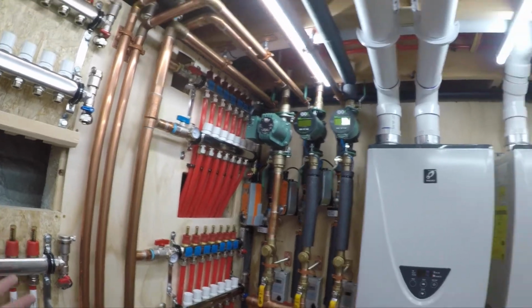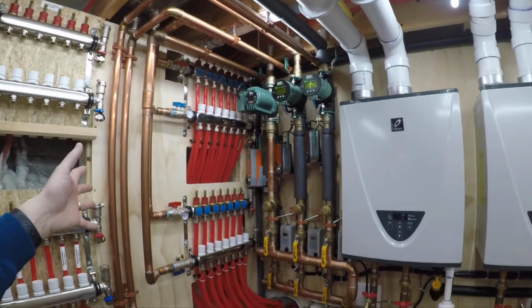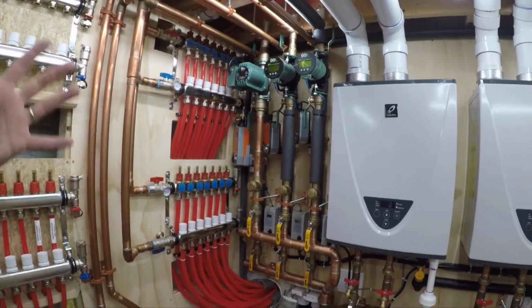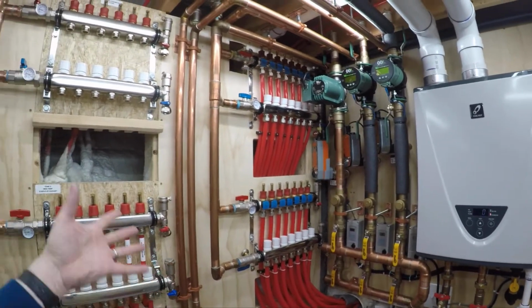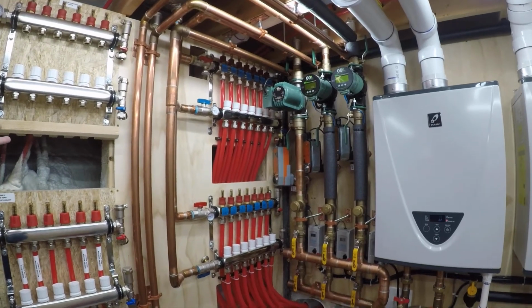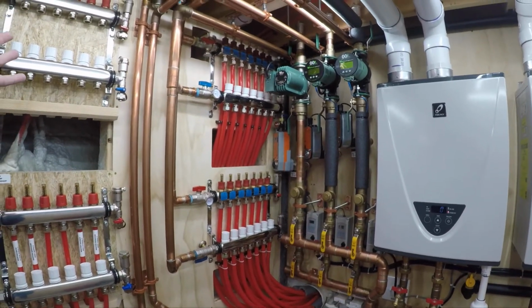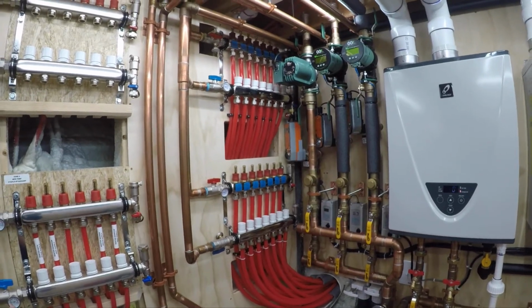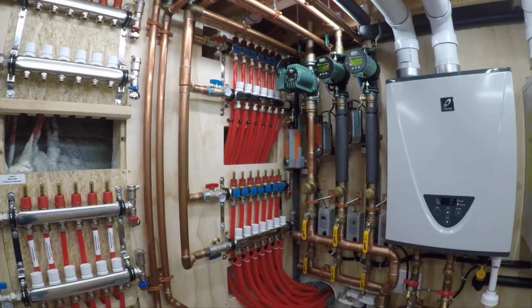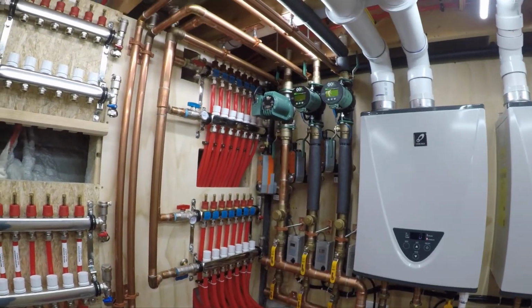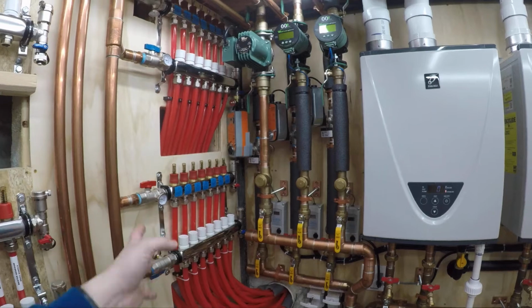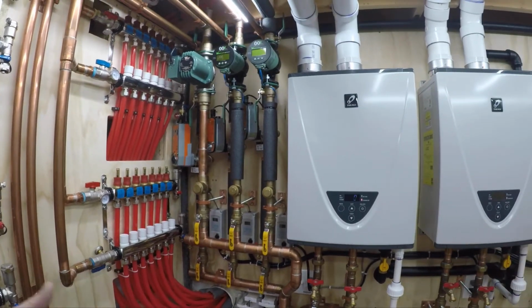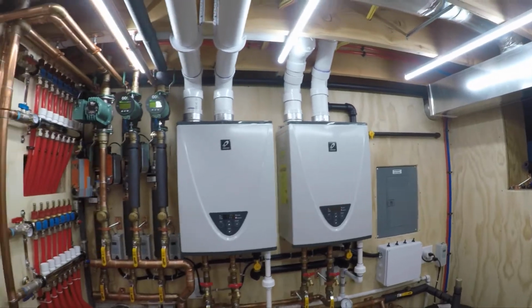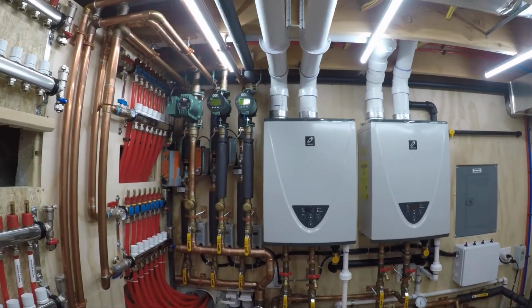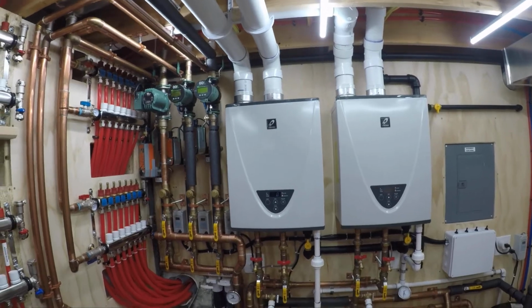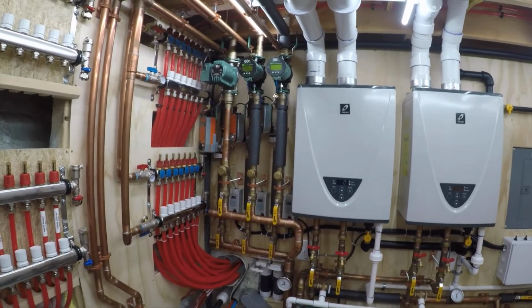So you don't need to be constantly dumping 130 degree water through this for hours and hours on end and bringing the surface temperature of the driveway up to like 60 or 70 degrees, when bringing it up to 45 will melt the snow and dry the slab just as well. And it'll do it very efficiently. So far, I like the setting of 80. That's what I have mine set to, and it just cycles like clockwork. It's firing these heaters twice an hour, sometimes 3 times an hour, for about 10 minutes each. And that's it.